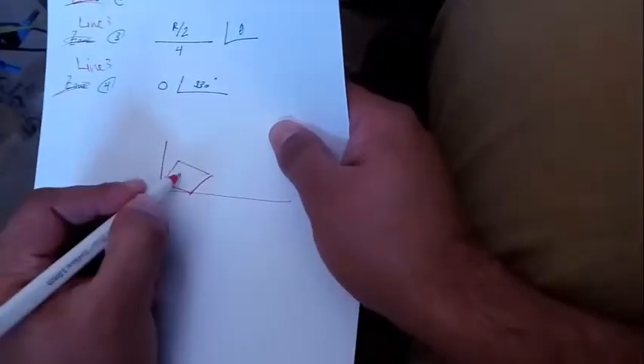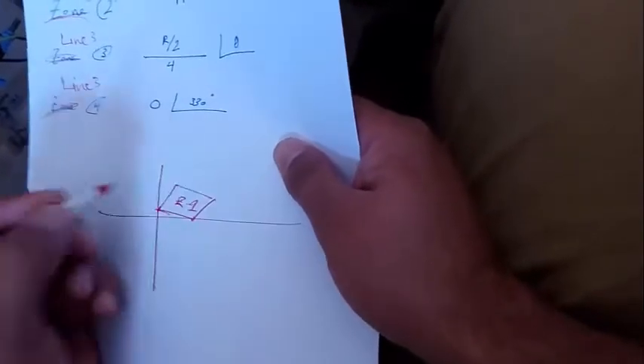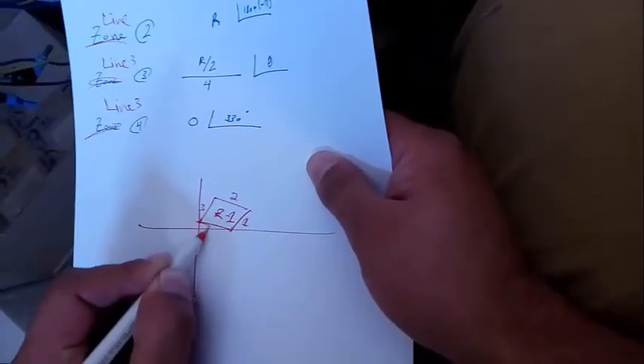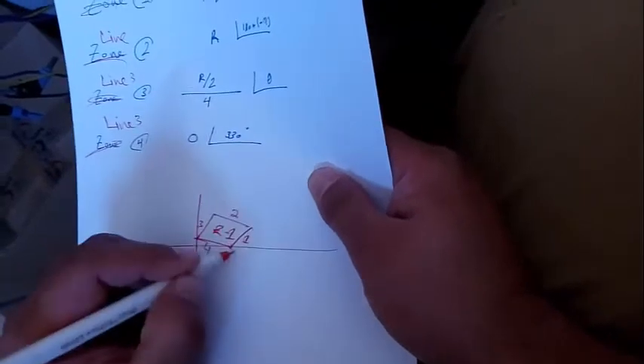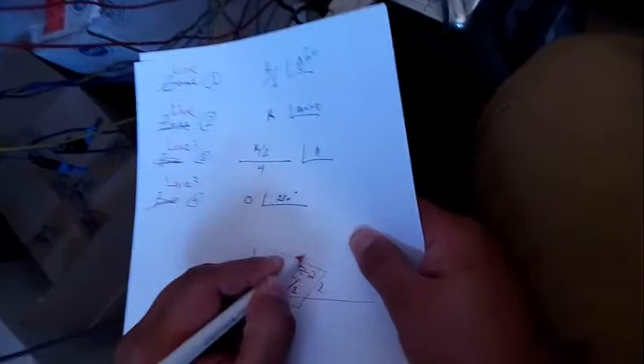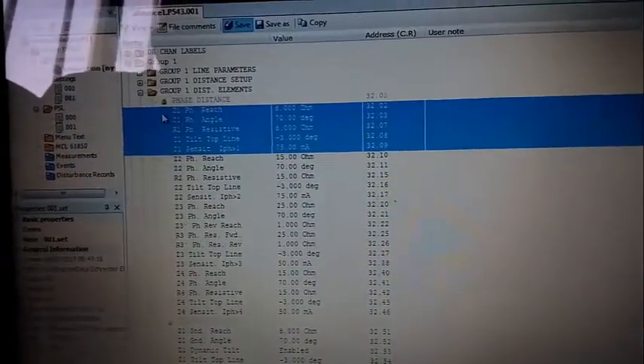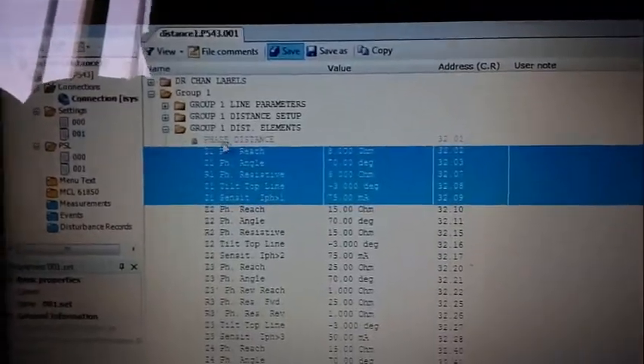We need to draw the limits of the zones. For example, for zone one we draw four lines — line one, line two, line three, and line four. Similarly for zone two, zone three, and zone four. In the relay settings, we go to phase distance since we are dealing with phase-to-phase distance. Here we can see zone one and zone three parameters.